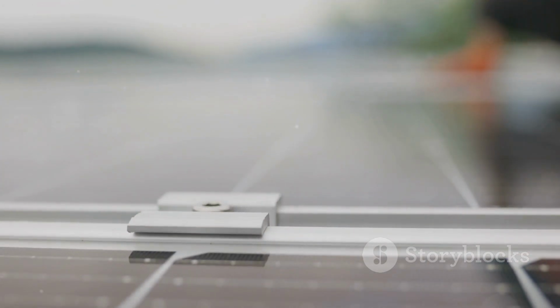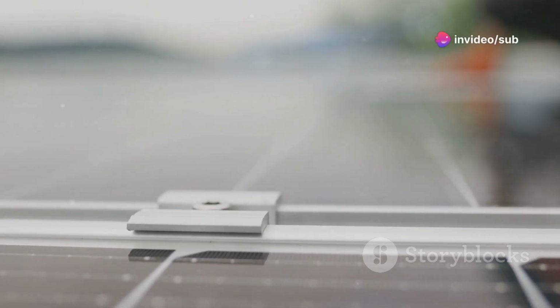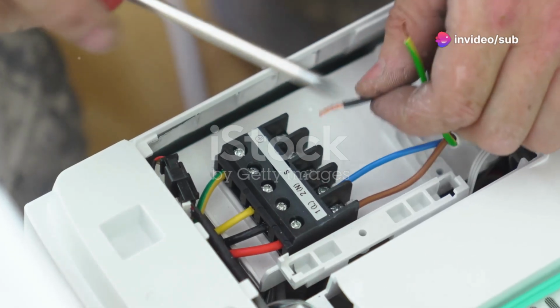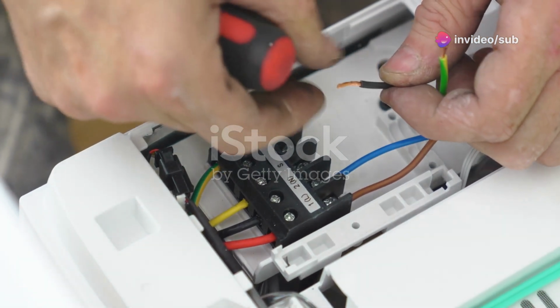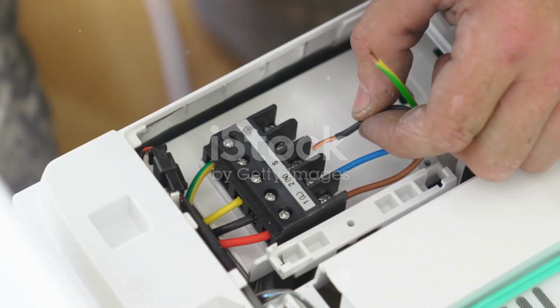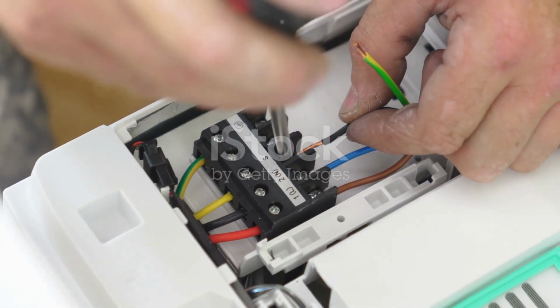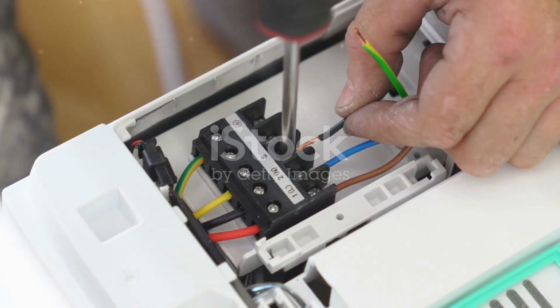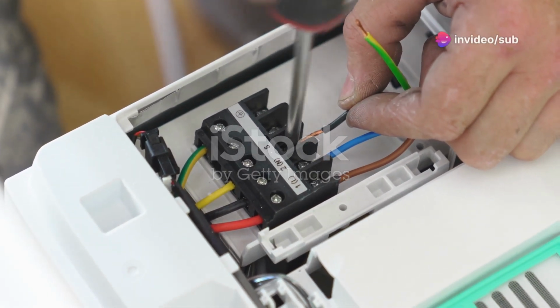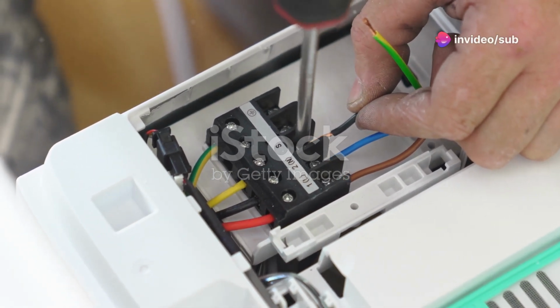Make sure the mounting surface is solid and level, as a secure installation reduces vibration and potential damage over time. Next, connect the DC cables from your solar panels and batteries to the inverter. These cables carry the electricity generated by your solar panels and stored in your batteries, so double-check that you're using the correct gauge and type of wire for safety and efficiency.